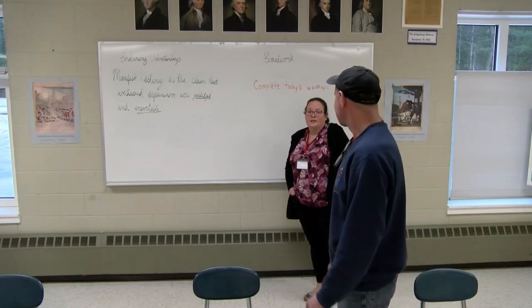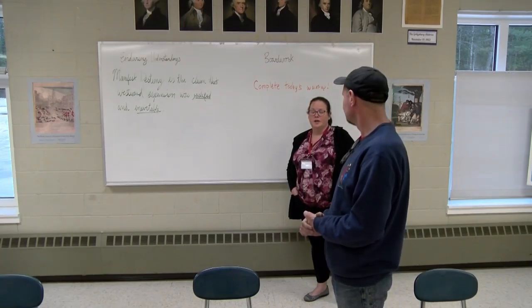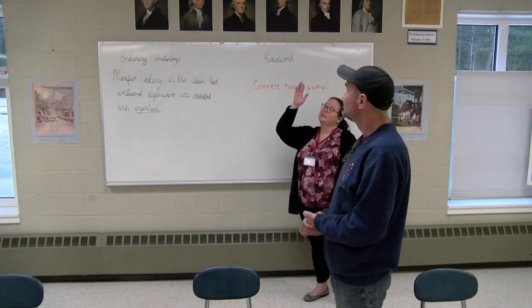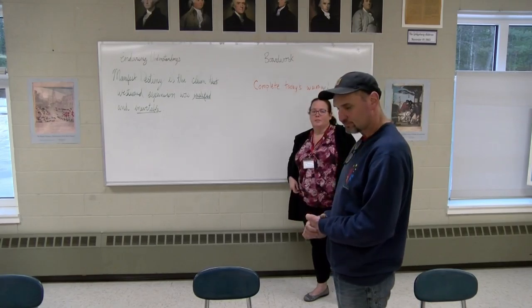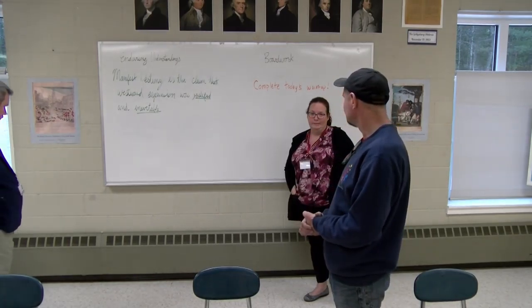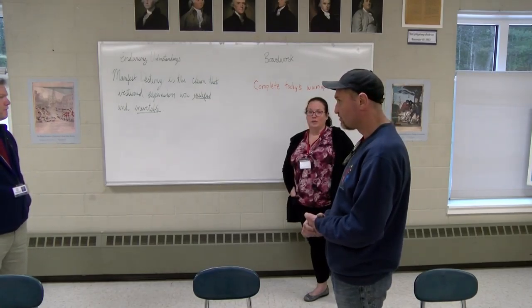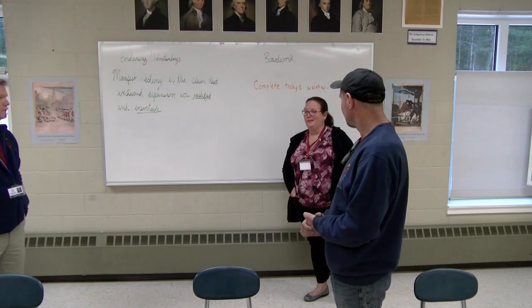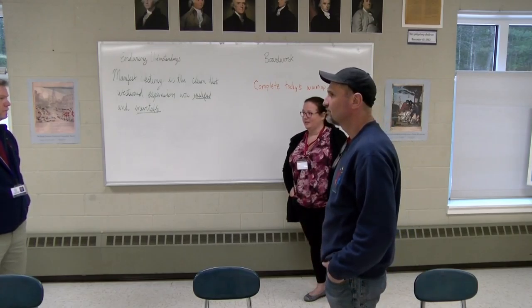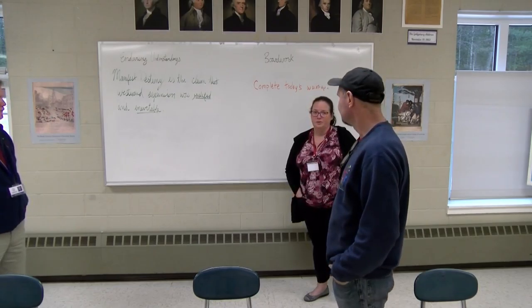I think we also talk a little bit about what that means for the comfort of our students when they're here in the classroom. Yeah. So as they're sitting and the cold air is coming from underneath, or the cold air is coming from up above, there's very varied temperatures with our students in a classroom in cold weather climate. When it's 12 degrees outside, the variation in the classrooms range anywhere from 85 with the super high heat blowing to 55 because of the cold air coming in. So we're trying to make that better for the learning environment for our students overall.